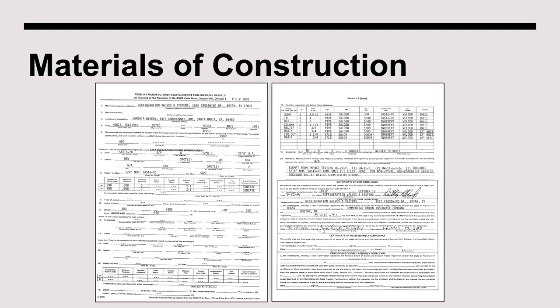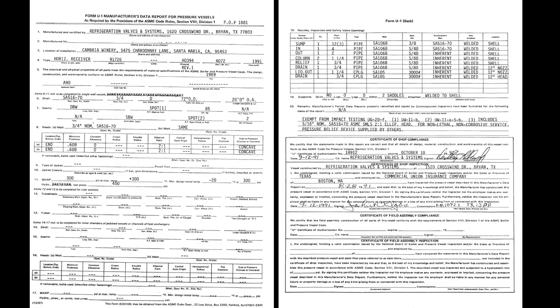When documenting the materials of construction for a high pressure receiver or any pressure vessel, the key document is the Manufacturer Data Report. A closer look shows that the U1 form describes the steel specification and thickness for both the head and the shell of the vessel. The next page includes a listing of all vessel connections, including the size, grade, and schedule of the nozzle.